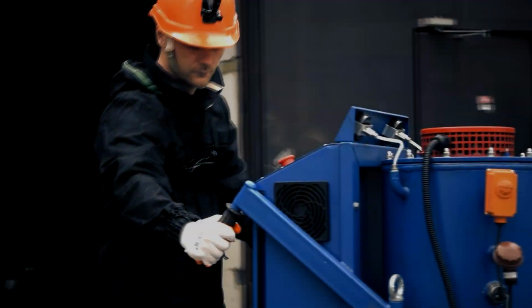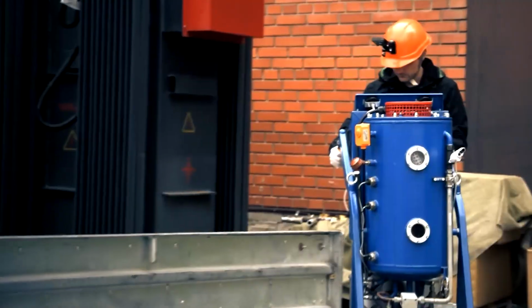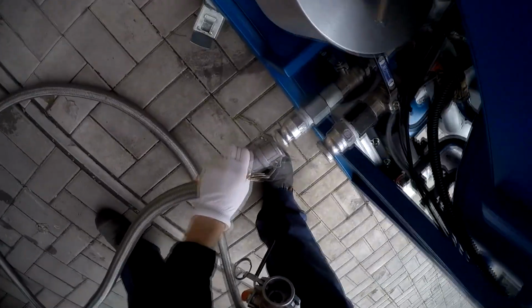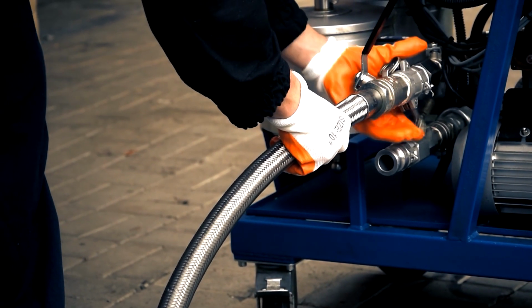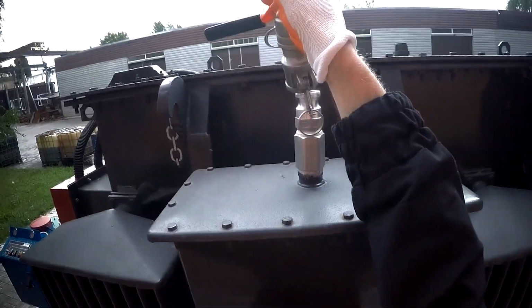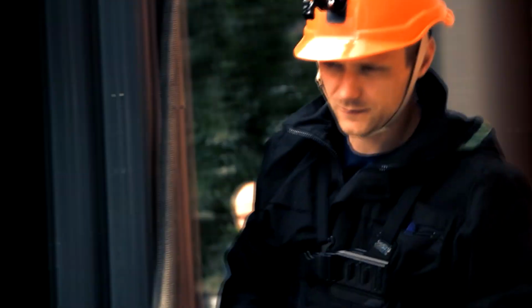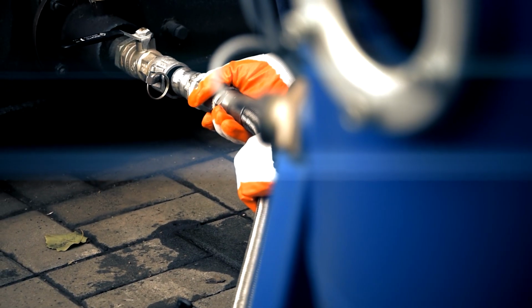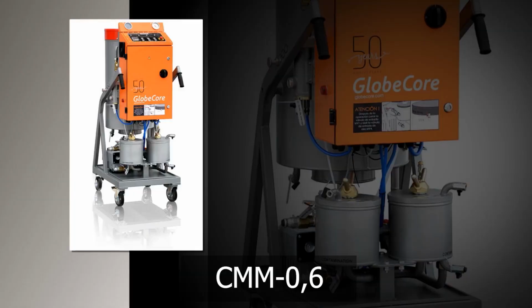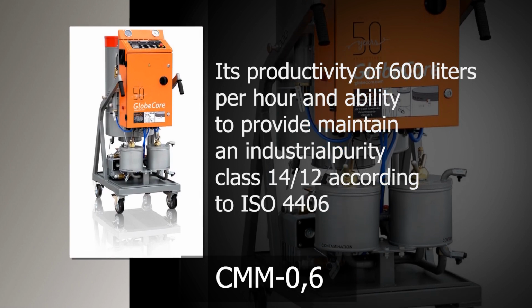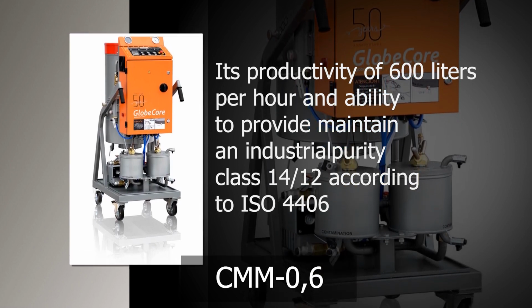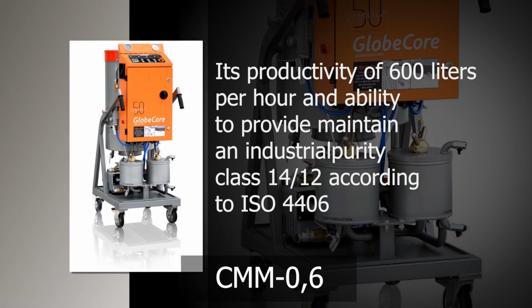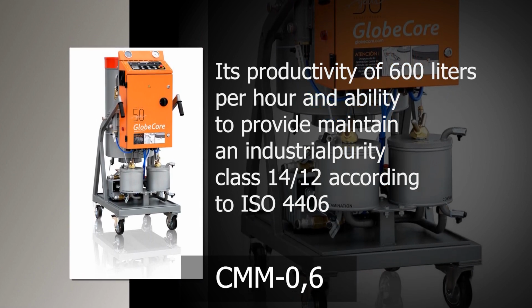This equipment is easy to maintain, compact, and has quiet operation. It suppresses foam formation and protects against oil leakage. But the benefits of the compact transformer oil purifier CMM-0.6 go beyond its compact size. It also has an ecological effect, helping to reduce waste and promote sustainability by enabling reuse of transformer oil. Its productivity of 600 liters per hour and ability to maintain an industrial purity class 14/12 according to ISO 4406 make it an effective solution for transformer oil purification.